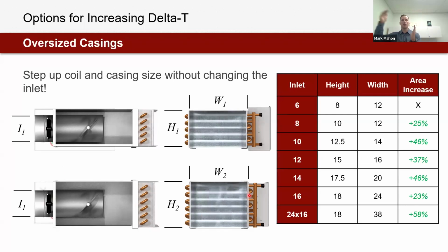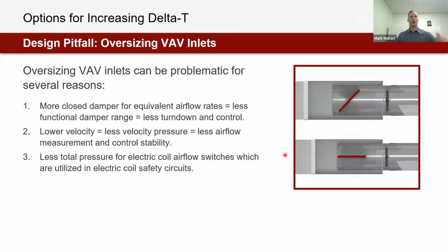Well, we're always stepping up one commodity size of casing while holding the inlet the same size. So for a small box, it's kind of like 25%. We have the one outlier of the size 16 stepping up, which is really only like 23%. But generally, we're living in a third to a half as roughly how much bigger we're going to be able to get that heat exchanger. And this option is important because the alternative, which I see happening from design engineers in a lot of cases, is just oversizing the whole VAV box. And that is not my recommendation. I think that's something we need to try to avoid as design engineers, because it can be kind of problematic.